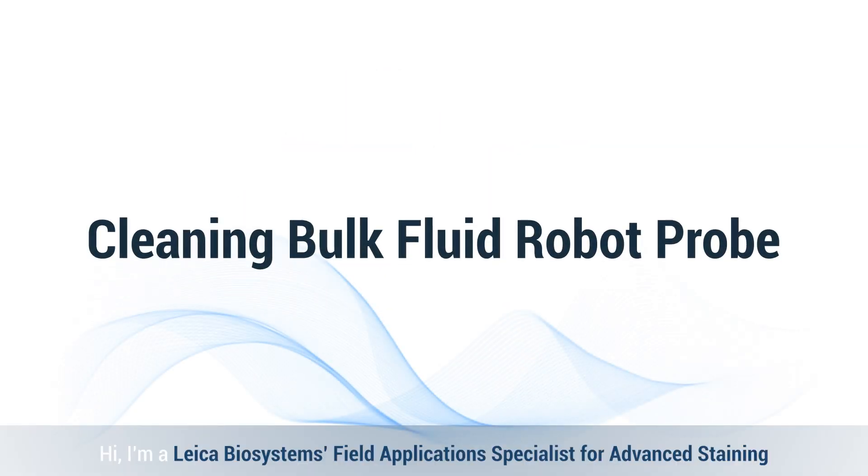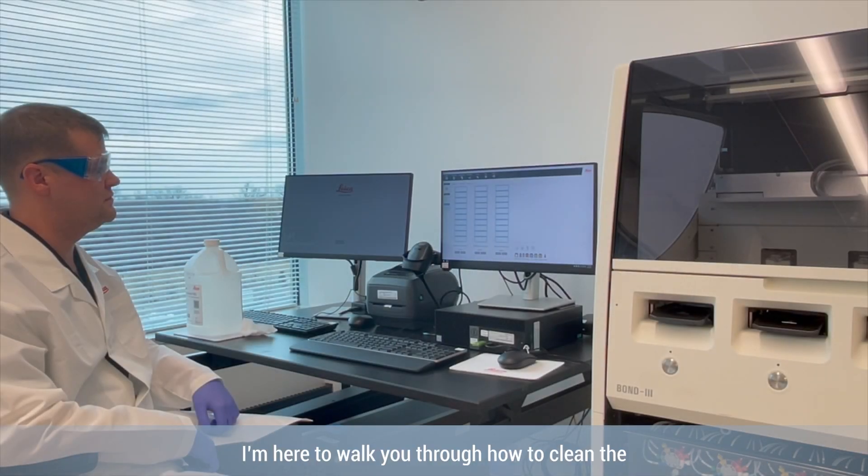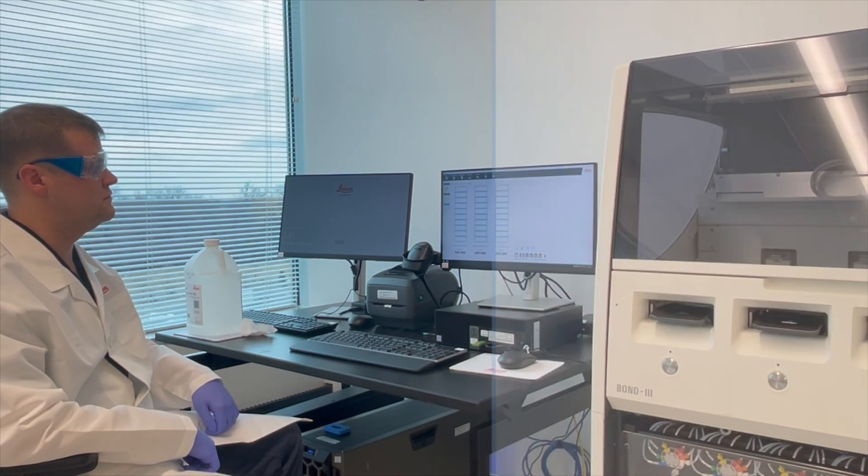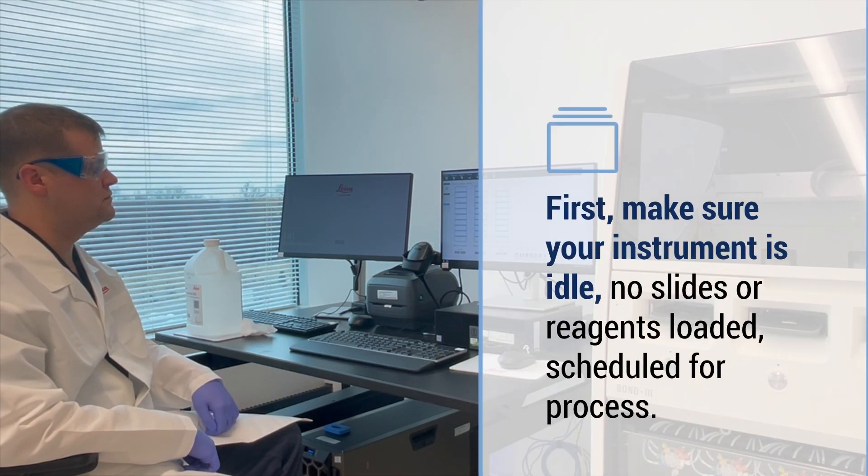Hi, I'm a Leica Biosystems Field Application Specialist for Advanced Staining, and here to walk you through how to clean the bulk fluid robot probe, also known as the BFR. This is part of the monthly maintenance process that might seem complicated but it's actually pretty simple. First, make sure your instrument is idle.